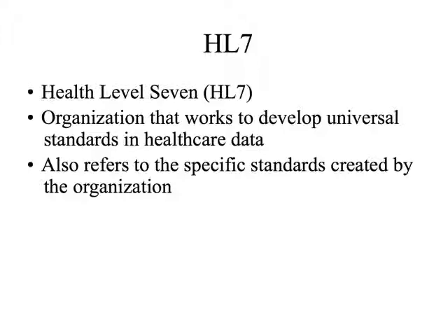That also means that, say, I had difficulty communicating with someone else's PACS. If I had a way to send stuff directly from the processing station to their PACS over the HL7, I could. So even if I can't get the PACS systems to communicate because their DICOMs aren't the same, I can probably figure out a way to patch in and send directly from the processor over an HL7.